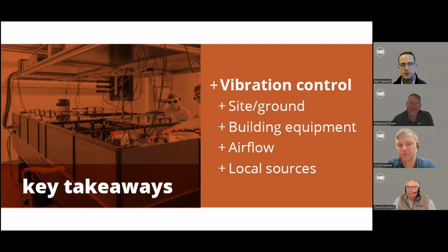That was new to me on that project, and that was a fun problem to solve. And then talking about local sources, they're going to need stuff. Scott mentioned compressed air. I think every single project we've done had a compressor. They want it close to the lab because that's where they're using it, but compressors vibrate, they're loud, they shake, so you've got to move them. In our particular case, they were adamant they needed compressed air near the lab before we identified how stringent the vibration criteria were. We ended up having to change the design and move the compressor to its own little building outside, a little shed, and feed compressed air in so we didn't create new problems.